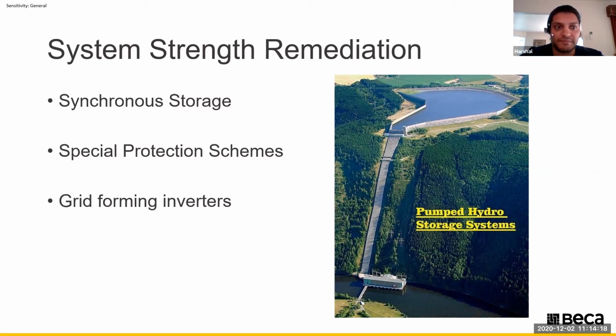Other options are special protection schemes to curtail generation output or trip under certain network conditions, such as contingency events. This doesn't directly improve system strength, but tripping of inverters under the right conditions will prevent system strength from worsening. Again, it's a trade-off against the cost of development versus revenue from generation. However, there's an opportunity to increase your total nameplate export capacity as network upgrades and augmentations occur over time, allowing you to export more without curtailing or running the risk of being tripped off.